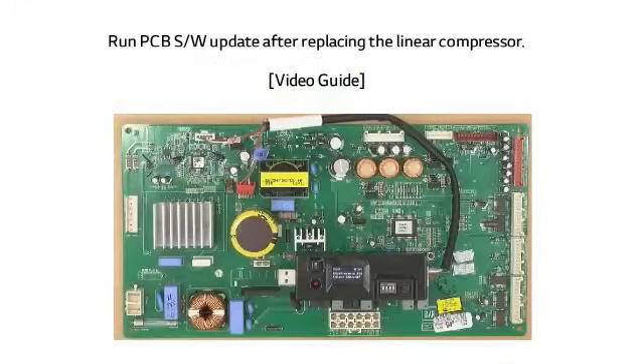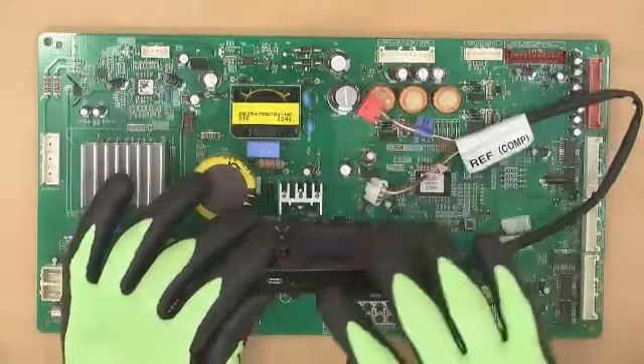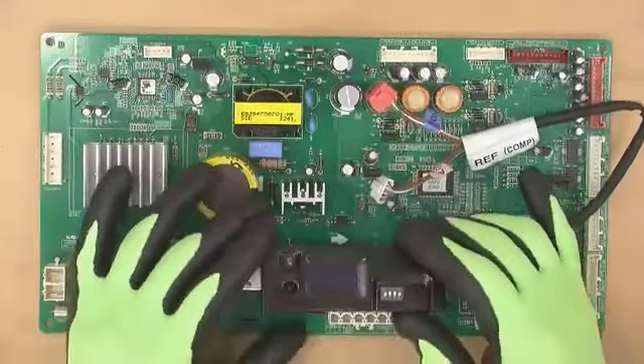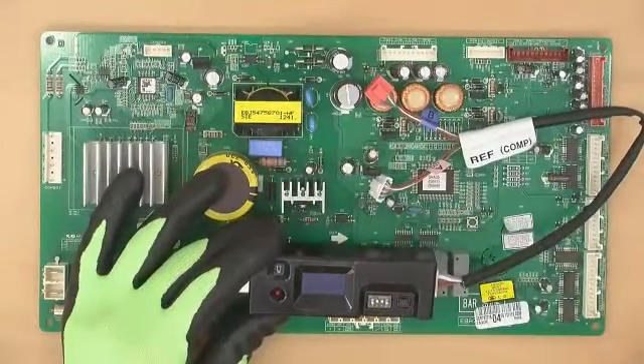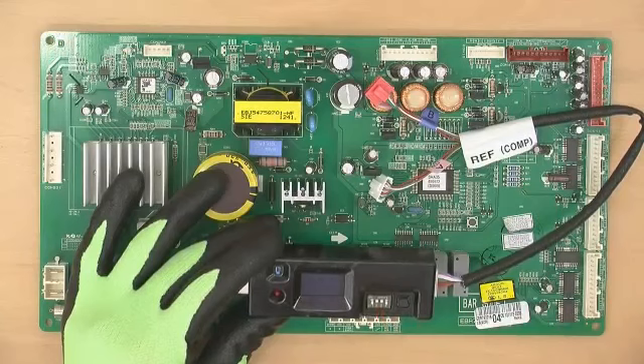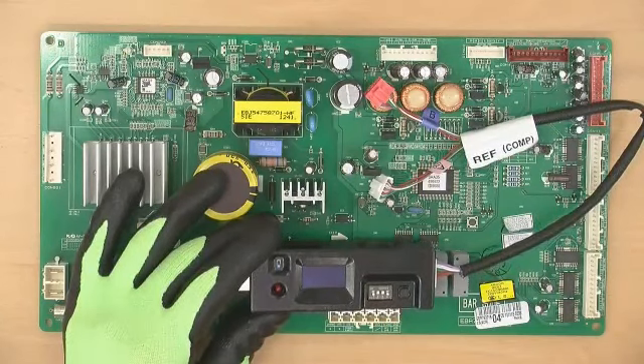Now let me show the actual method of PCB software update based on refrigerator's linear compressor replacement. First, unplug the refrigerator. Second, check if the SD card is inserted properly. Third, set the DIP switch — turn OFF numbers 1 and 4, and turn ON numbers 2 and 3. Fourth, remove the PCB cover.